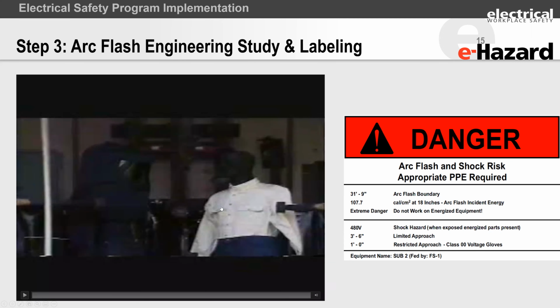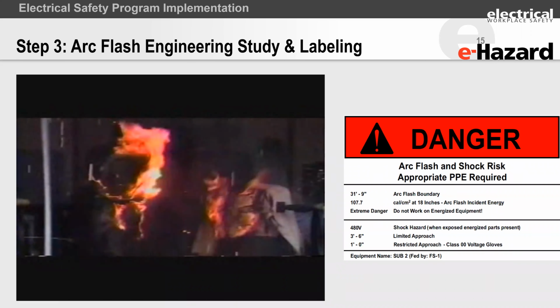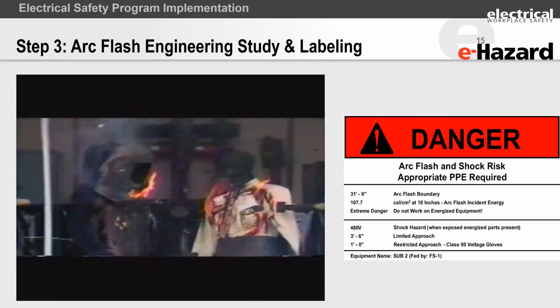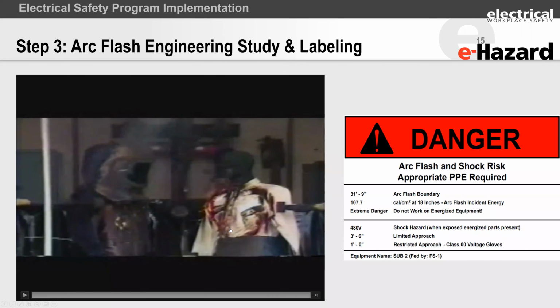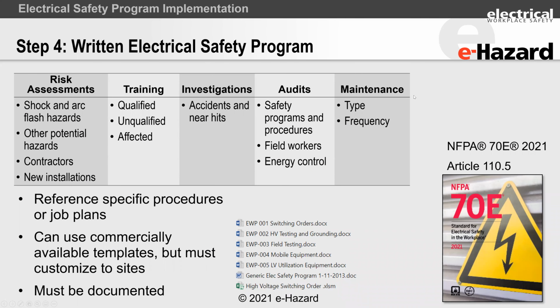Now, we've been talking about, hey, even if you don't know what the energy is, roll out 8 to 12 calories per square centimeter. But what I want to mention to you as well is that this clothing does have limitations. So here what we did was we put a mannequin in a flash suit and we put a mannequin in category 2 type of clothing, 8 to 12 calories per square centimeter. And we hit both of these with the arc flash, and the mannequin that had the flash suit on received no burns, while the one with daily workwear received second and third degree burns. Now, although you don't have the ignition of arc-rated clothing, you still have incident energy transmission from the equipment through the body of the worker. And that's where you see these incidents. So be careful about the limitations of daily workwear and the need for flash suits in certain instances.